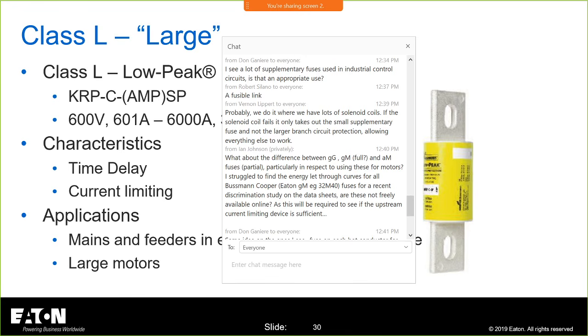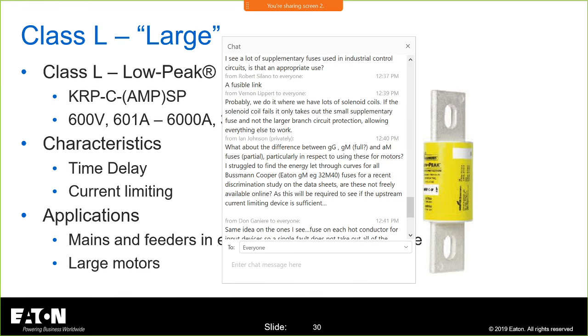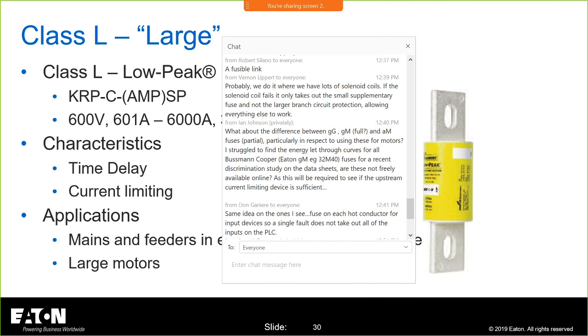Probably we do it where we have lots of solenoid coils. If the solenoid coil fails, it only takes out the small supplementary fuse. Yeah, there you go. Not a large branch circuit protection. Right. It's a good case of using it where you don't necessarily have to, because you still have that overcurrent protective device upstream. But if you have a specific reason inside of an industrial control panel to isolate something, should you have a problem, you don't extend the damage beyond.